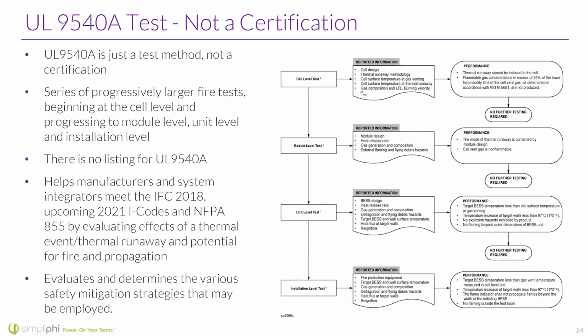Basically, this has a lot to do with fire safety. A series of fire tests, progressively getting larger, are done on the batteries. Our testing came out great. It actually allows us to have looser guidelines on things like sprinkler systems when an AHJ is looking at the 9540A test results of that specific ESS system or battery and making calls. So we've gone through that process as well. We've got tons of press releases out if you're interested in hearing more about that 9540A testing.